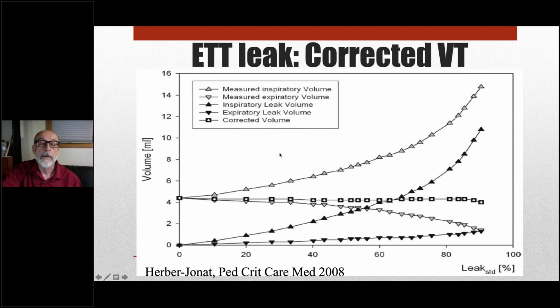And in this graph, there's actually the calculated value. The leak compensated value is here, and you can see that the actual tidal volume was a little over 4 ml, about 4.5 ml, and you can see that the calculated value remained extraordinarily stable all the way up and beyond 80% leak, which is quite remarkable.